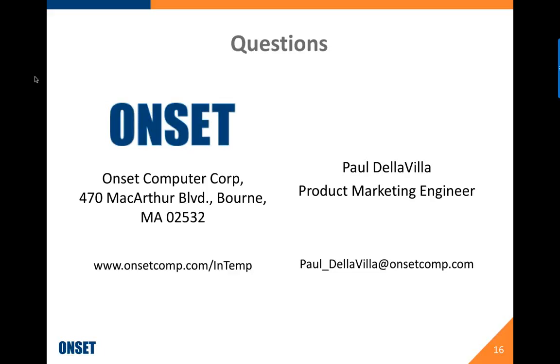The first question, will it alert or alarm remotely to your phone or email? Do you have to download it first? You do have to download it, but we have a number of options within our mobile smartphone app to start to automate that, including some gateway technology that will actually be out in the next couple of weeks that you can set up within a clinical site to automatically download information in the event of an excursion.